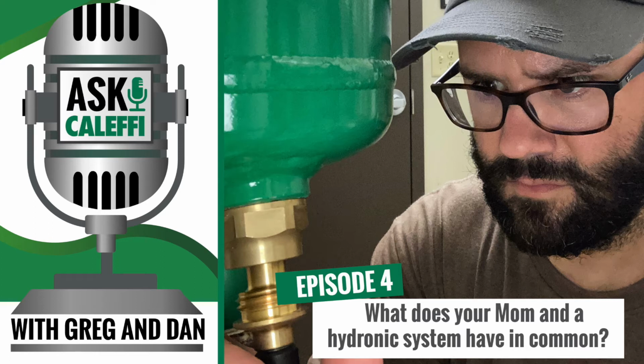That's right. Yeah, so it's got a very small pressure drop across the vessel. Right, that's because of that large body. Right, it's very negligible. It was a lot like that air separator last week with the large body, your velocity drop. So essentially there's low to no pressure drop. Right, and we do list CVs in our literature, but honestly, you could pretty much ignore it in your head loss calculations. There's guys that won't, though. They always want every little detail. And you can do that. But I think, you do that enough times, you're going to find that it's so negligible that you'll probably stop doing it.